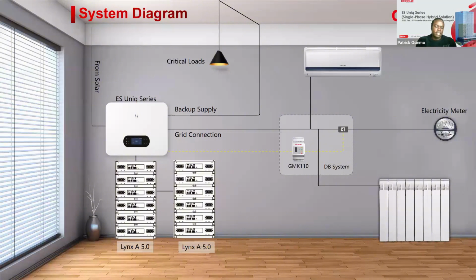The inverter also comes with a standard CT cable, but that's not a fixed way of installing it. There's an option of including a smart meter in between, in case you want to do long distance communication. The smart meter to the inverter can achieve up to 100 meters communication length, and you'll still be able to accurately monitor. Accuracy is key in this installation option - if you want more accuracy for longer distance, include a smart meter in between.